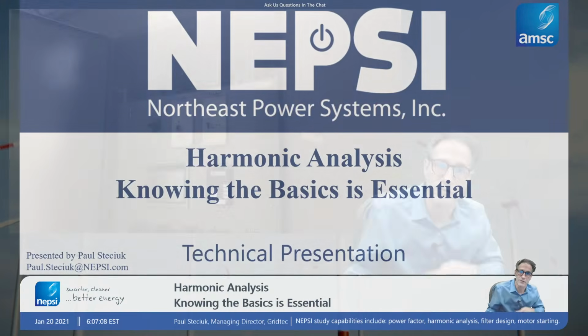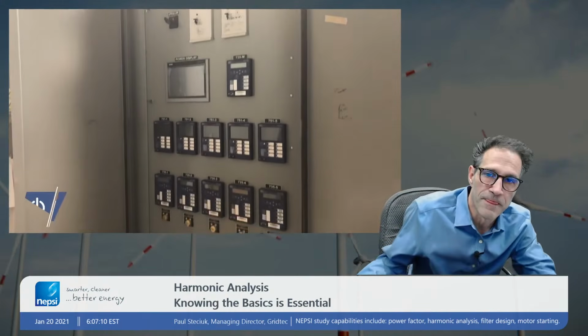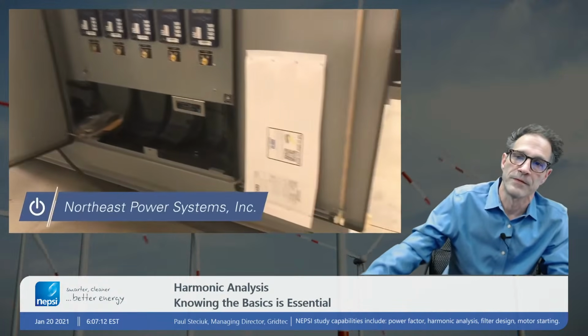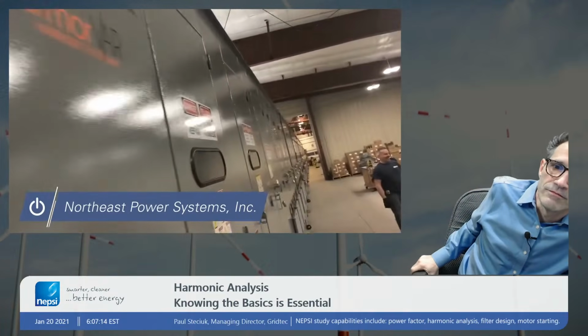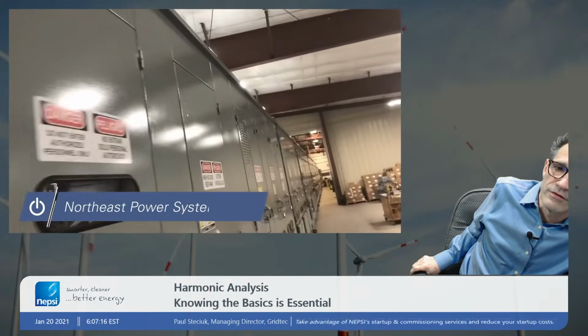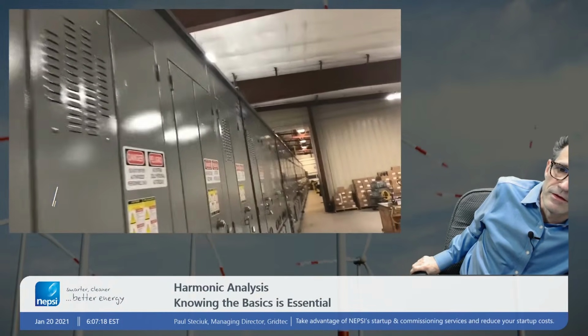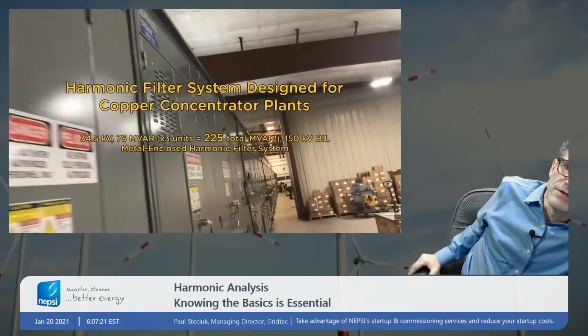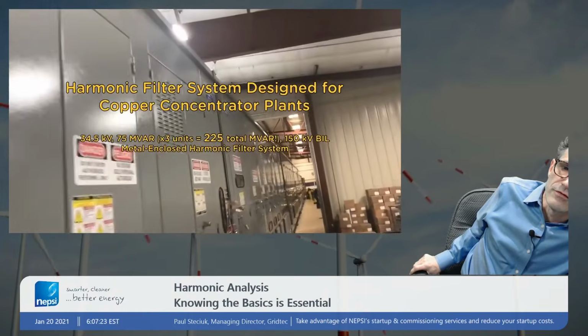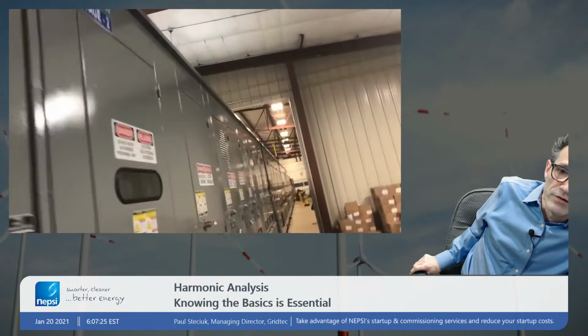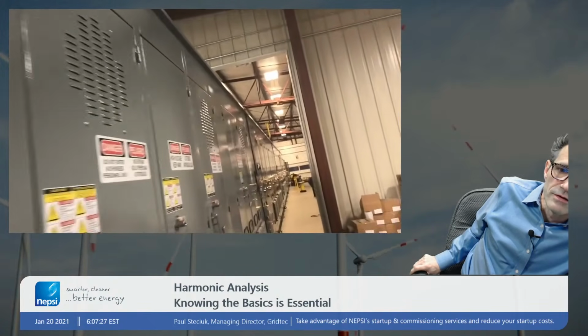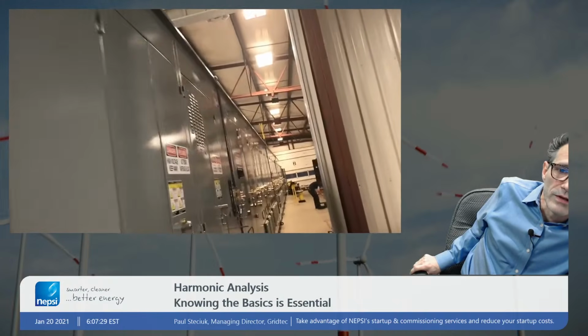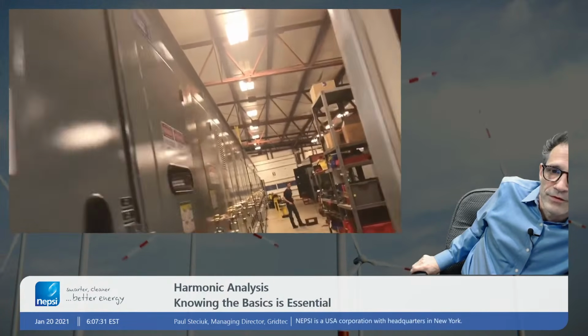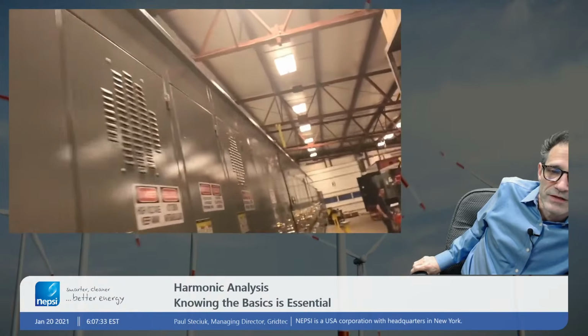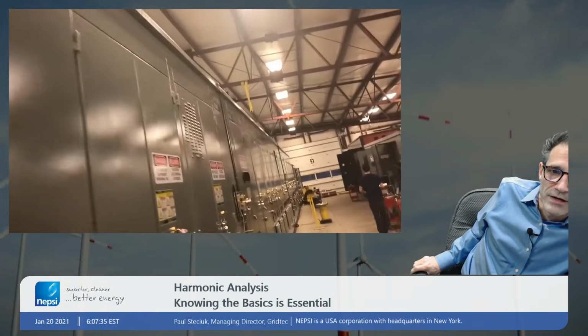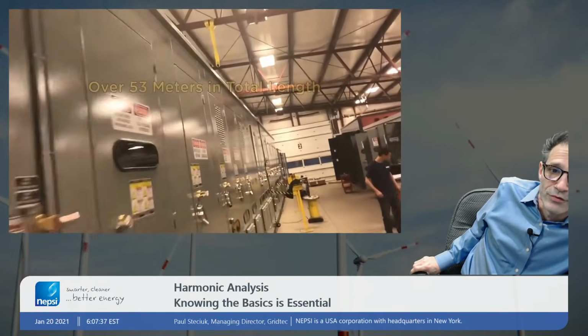And before we get on, I'll show you one quick large harmonic filter system here. This is a 75 megavar shunt harmonic filter system built in our factory in Queensbury, New York. So we ship these harmonic filters from our factory into various locations, mines, solar plants, wind, and so on, petrochemical, basically anybody using a lot of reactive power with nonlinear loads.